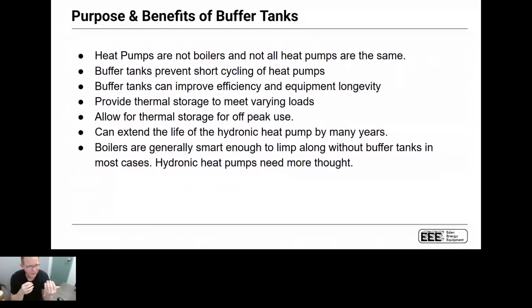Some of the key things to keep in mind as we talk about buffer tanks is that heat pumps are not boilers, right? That is a really, really important thing to recognize. What that means predominantly is a boiler can lift the water of a system 30 degrees, no problem. An air-to-water heat pump can't. So we need to make sure we decouple the outdoor unit, the air-to-water unit, from the inside system. Because typically on the inside system, we could be running at a 20 or 10 degree delta T, and we want to make sure we don't have a load mismatch there.